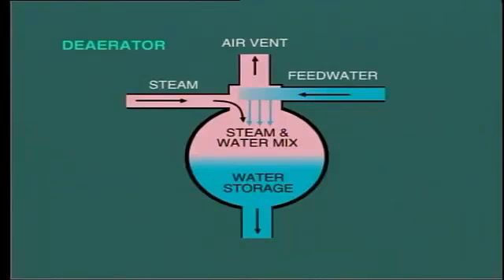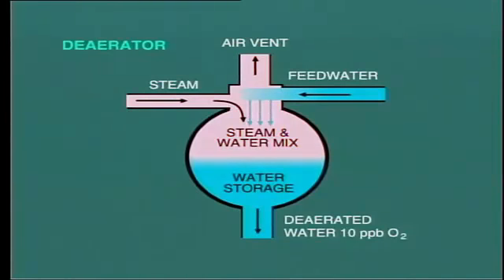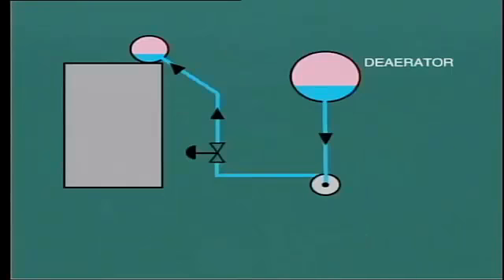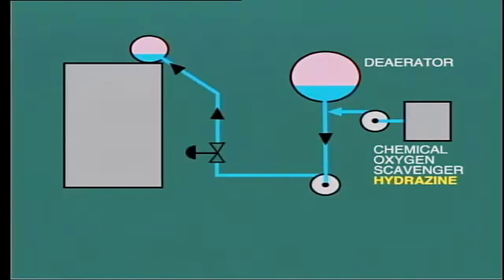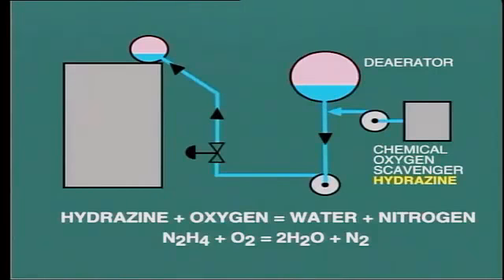A common cause of corrosion in boilers is dissolved oxygen contained in the boiler water. When oxygen is present, it causes severe pitting on metal surfaces such as the boiler drum and water tubes. Carbon dioxide, another dissolved gas, is also highly corrosive as it turns to carbonic acid. It is extremely important that dissolved oxygen and other gases such as carbon dioxide be removed or at least reduced to a very small value before the feed water enters the boiler. This process takes place in the deaerator, located in the condensate and feed water system. Modern deaerators can reduce the dissolved oxygen content in feed water to about 10 parts per billion and even lower.